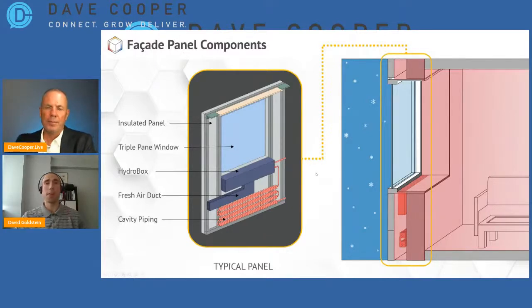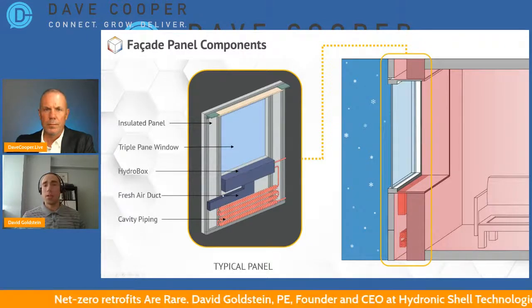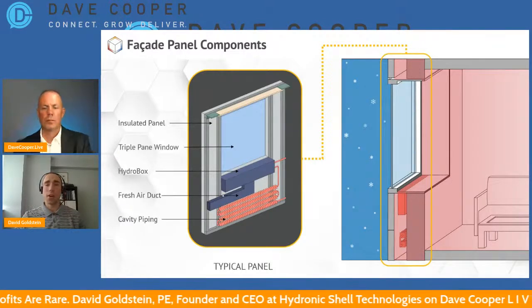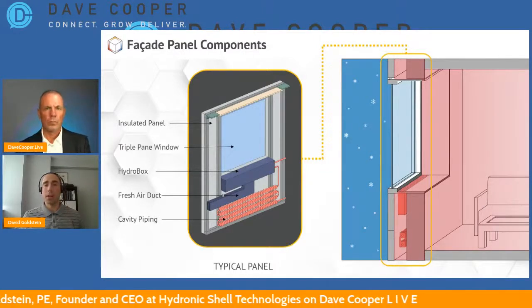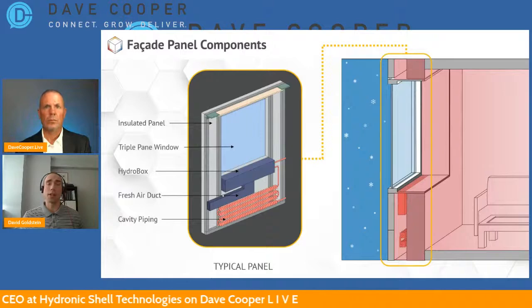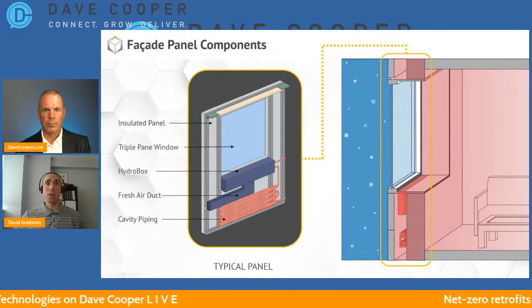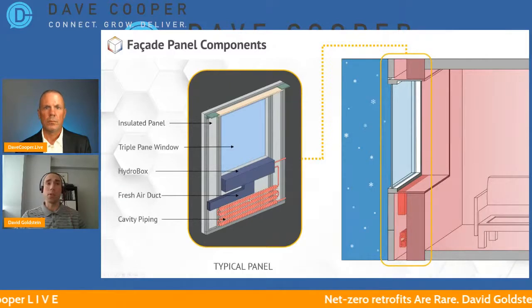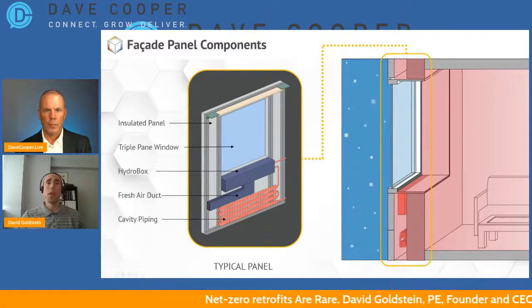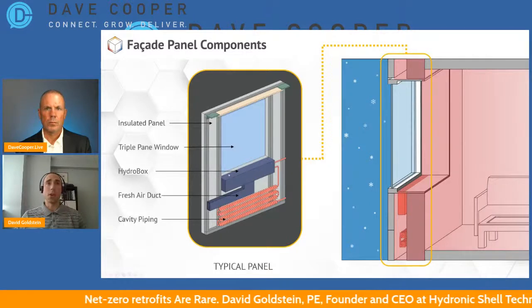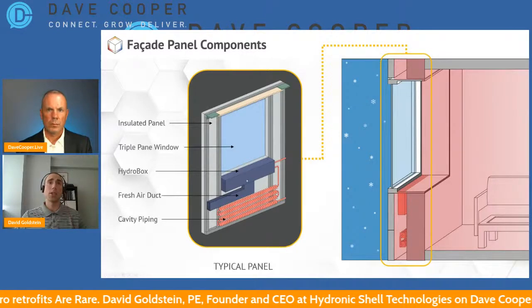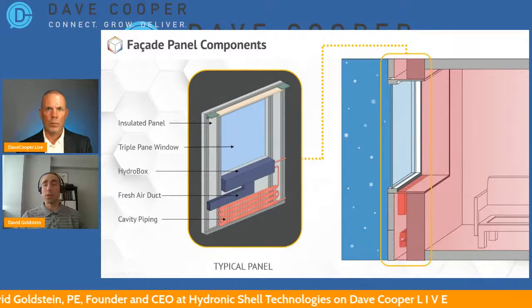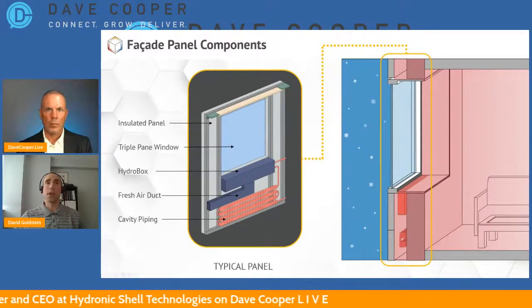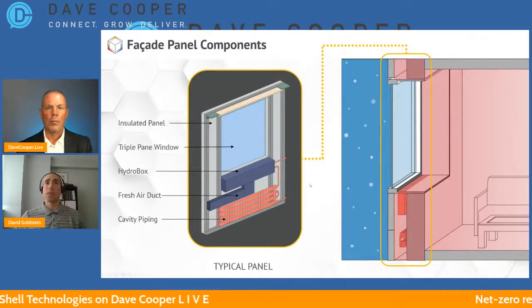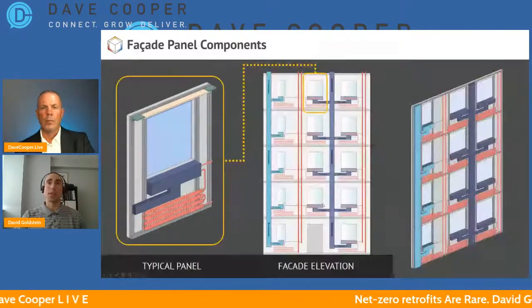So this is that prefabricated panel. Basically, the facade part of that panel can be any existing facade technology out there, from other facade panel manufacturers already making these kinds of products. It can be that same product essentially, but then all we do is integrate our HVAC components into it - the radiator piping that's heating up the cavity, the slim fan coil unit we call the hydro box, and the fresh air duct that's delivering air to mix into what the hydro box is circulating. That's what we're installing over the existing facade.